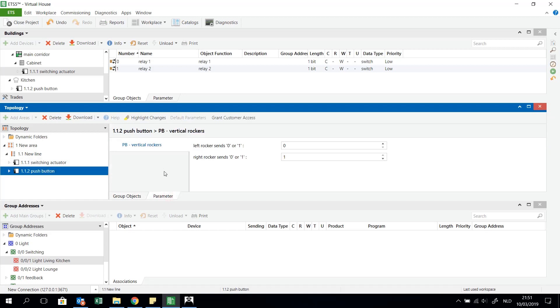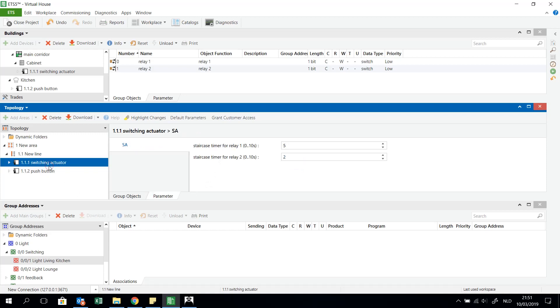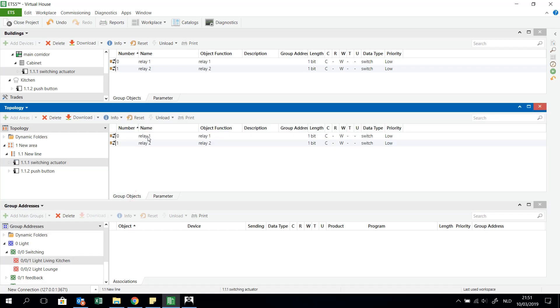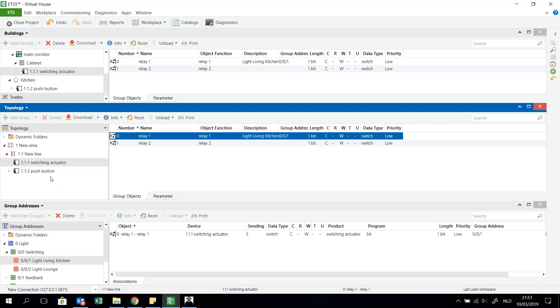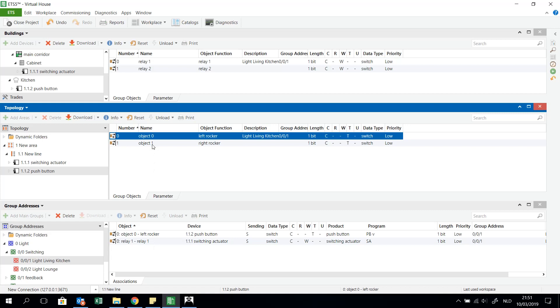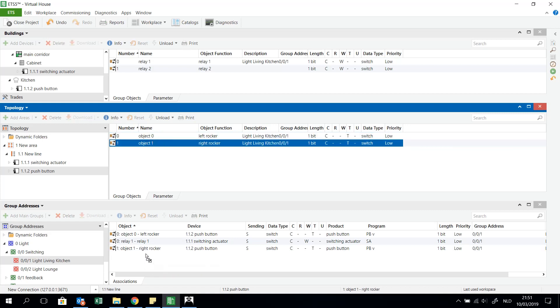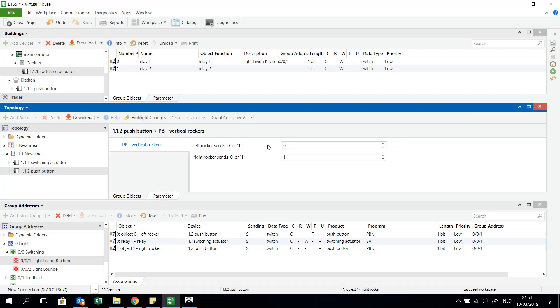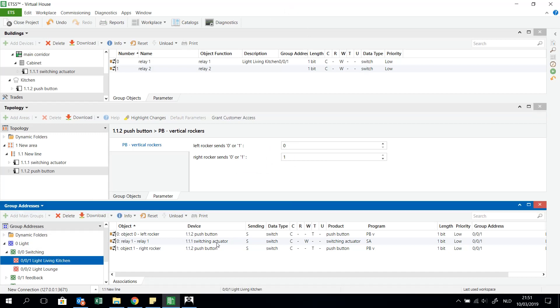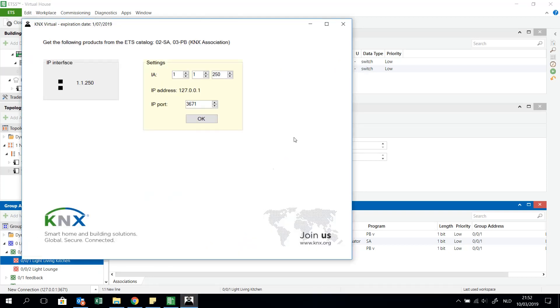Then I have the push button. In my parameters I can send a 0 or a 1 — it doesn't matter which you choose. I choose for example left rocker sending a 0 and right rocker sending a 1. Now I am going to work with those group objects. I start with relay 1 — I will switch a light on or off, or start the staircase function. This means when I turn on the light it will be on for 5 seconds, and I can also immediately switch it off. So left was off and right was on, just as an example.